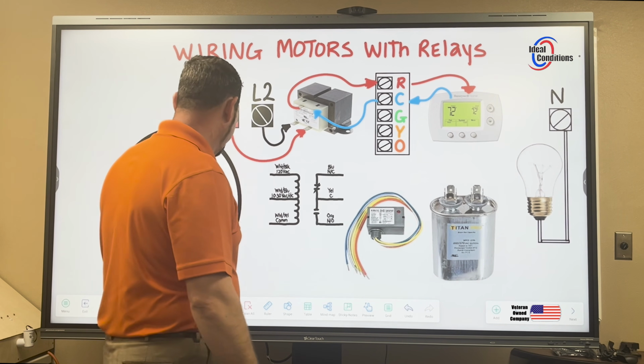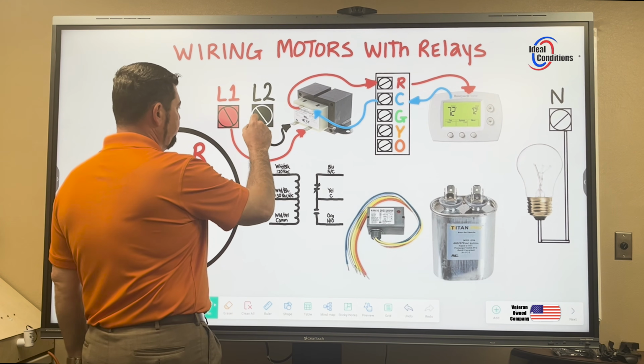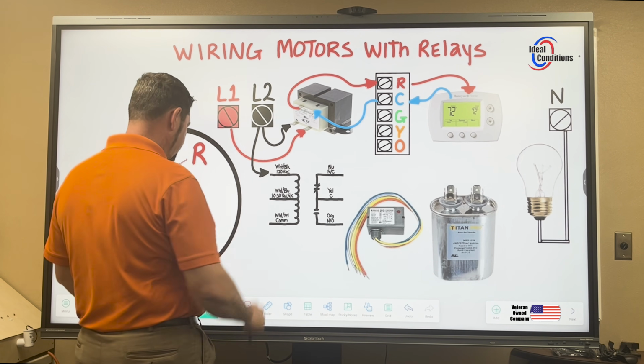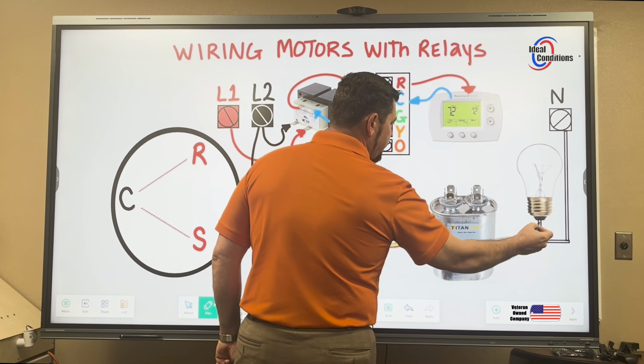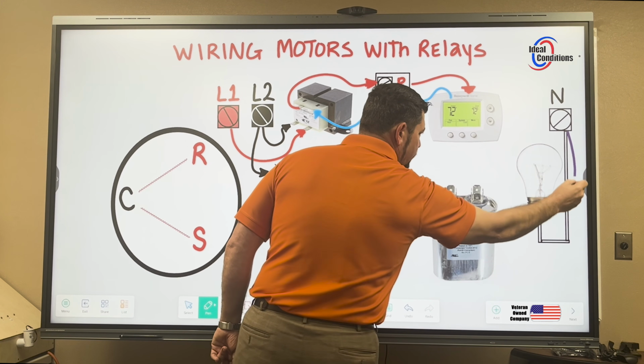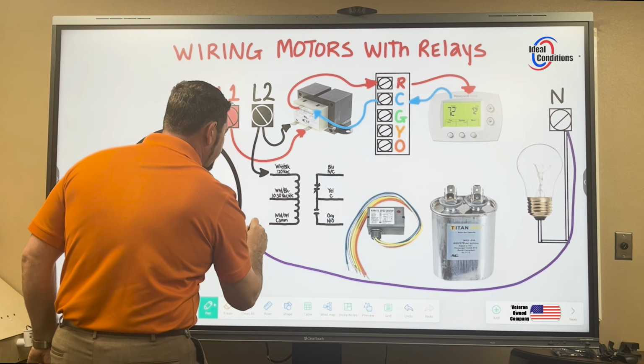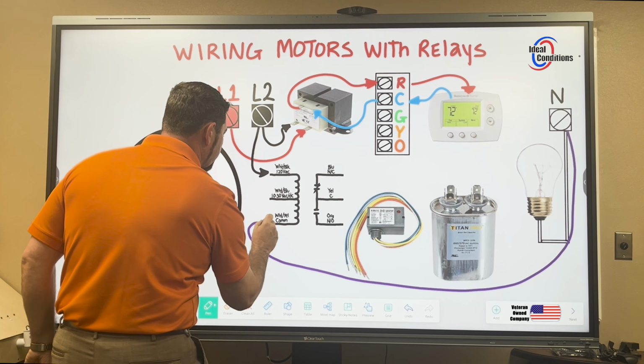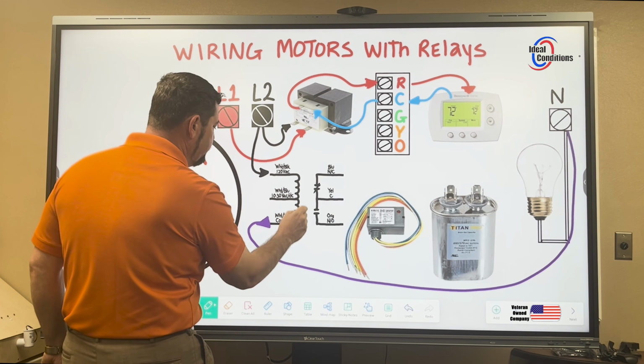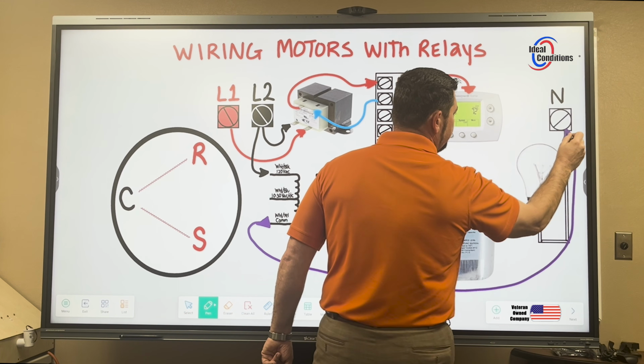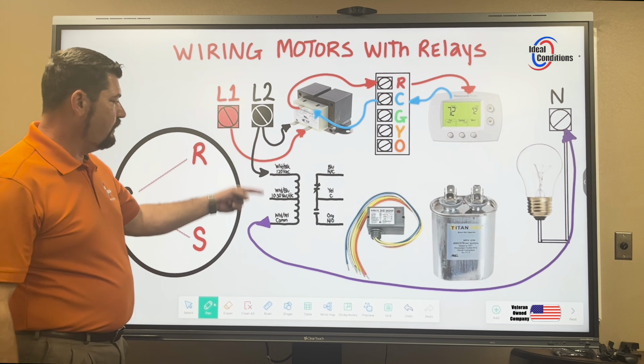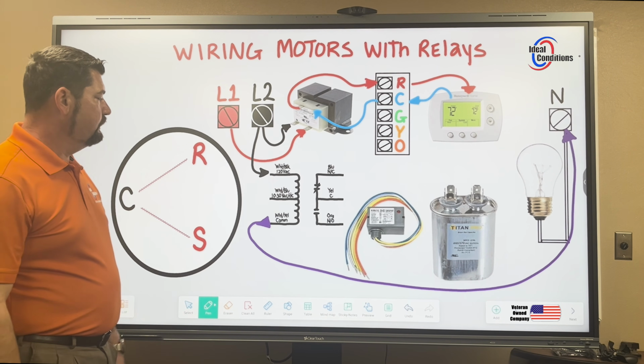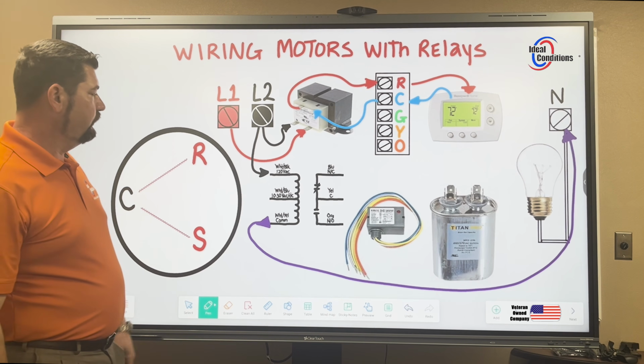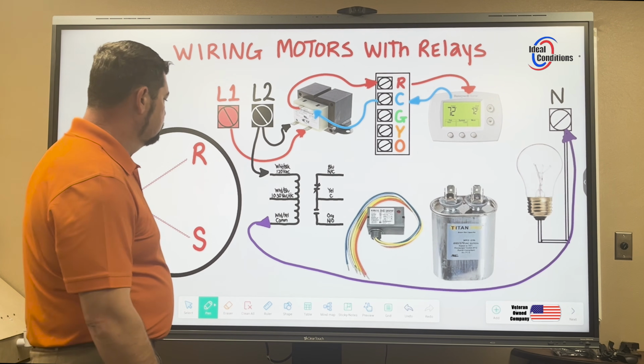And if I wanted to just come down here and say, let's put 1 leg of power right here on the 120. Then I'm going to go ahead and take, let's use neutral here, or purple for neutral. I'm going to come out of here and say purple, which is going to be neutral, would have to be here, and I'm going to draw my arrow going back towards neutral, because this would be an input, this would be an output, and right here, this would be an input. All right, and so now I can take that 120 and I can say, hey, you know what? I want 120 to energize my motor constantly. I don't know what you would do that for, but we're going to go ahead and have fun with this thing.